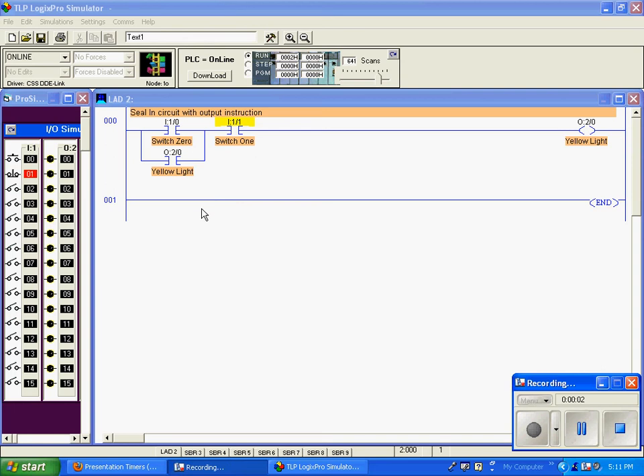Here I'm going to demonstrate a seal-in circuit using an output instruction. You'll notice that this output — our yellow light — and this contact has the same address as this output. You can consider this an auxiliary contact associated with this output instruction.